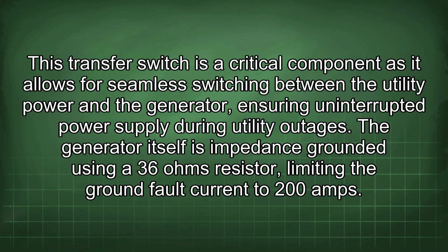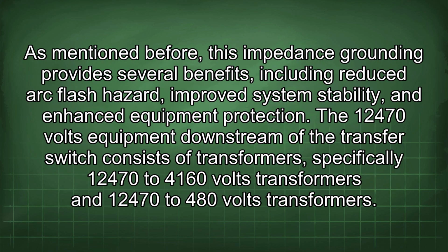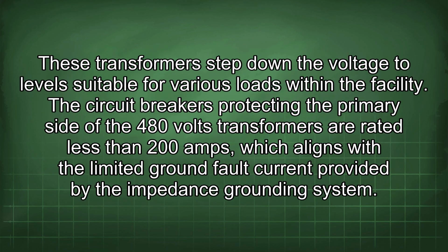The generator itself is impedance grounded using a 36 ohms resistor, limiting the ground fault current to 200 amps. As mentioned before, this impedance grounding provides several benefits, including reduced arc flash hazard, improved system stability, and enhanced equipment protection. The 12,470 volts equipment downstream of the transfer switch consists of transformers, specifically 12,470 to 4,160 volts transformers and 12,470 to 480 volts transformers. These transformers step down the voltage to levels suitable for various loads within the facility.